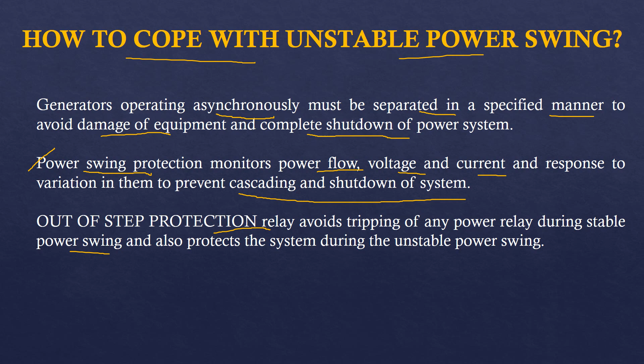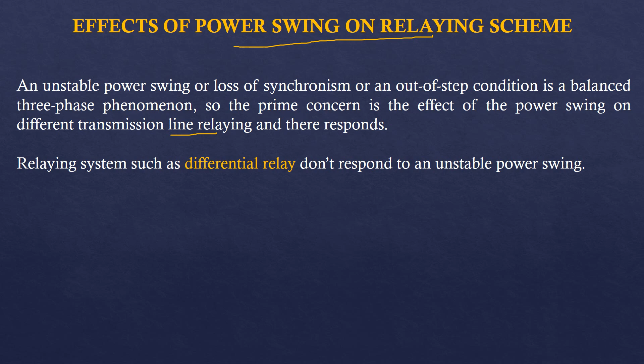Effect of power swing on various relaying schemes. Here we will be discussing which relaying scheme operation gets affected as a result of power swing. We know that the unstable power swing is a balanced three-phase phenomenon. So, majorly transmission line relaying schemes are affected by the unstable power swing. If we talk about the differential relay, then this relay system is not affected as it doesn't respond to the unstable power swing.